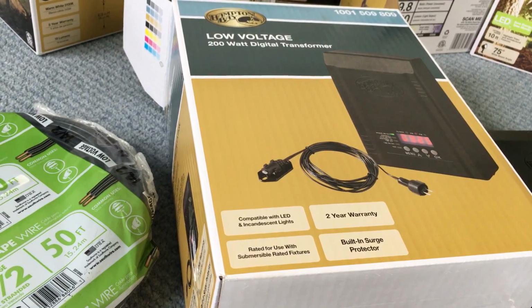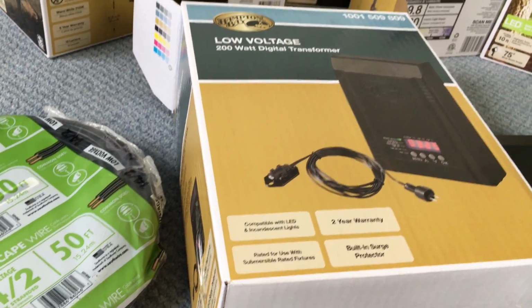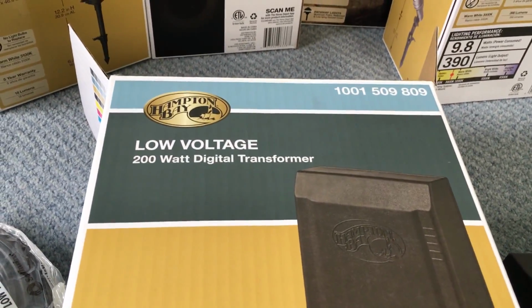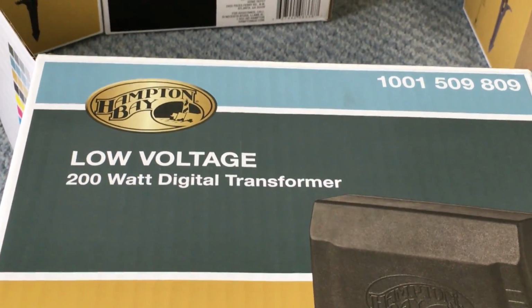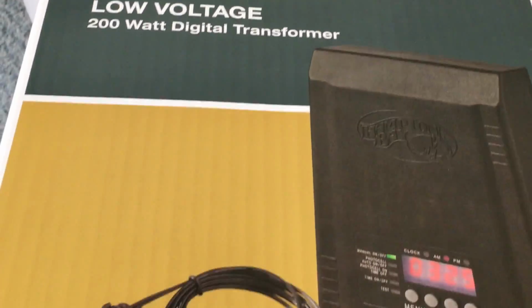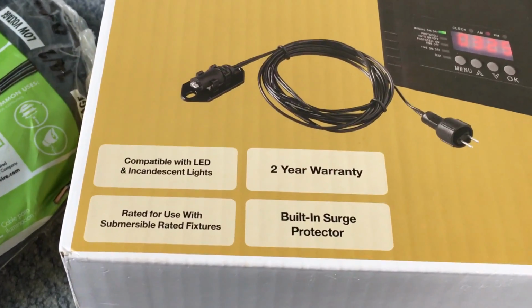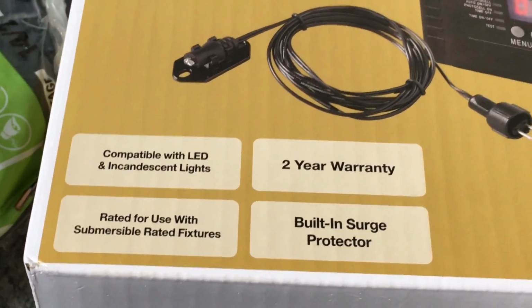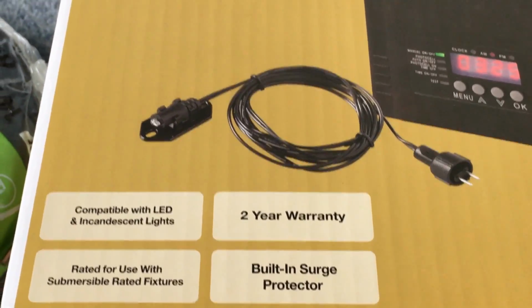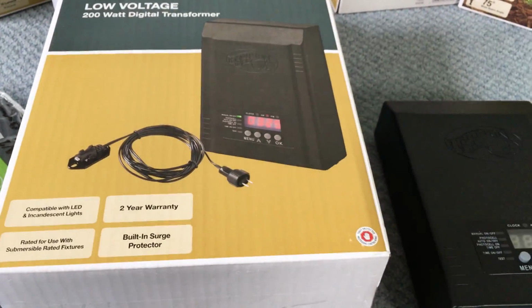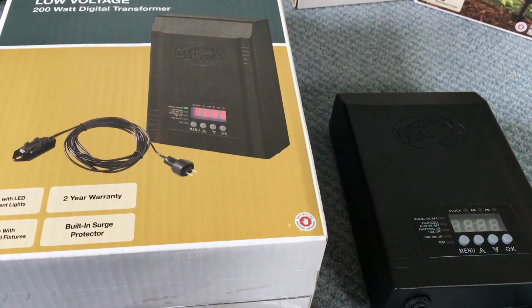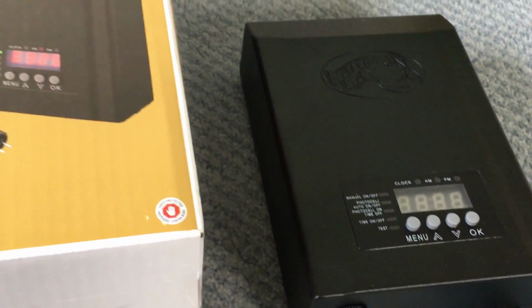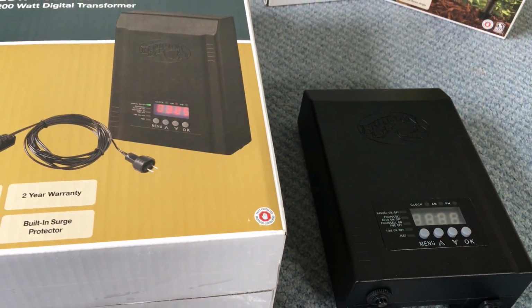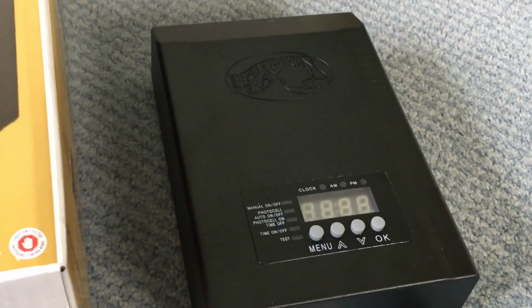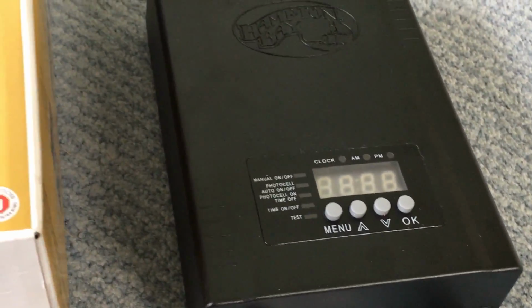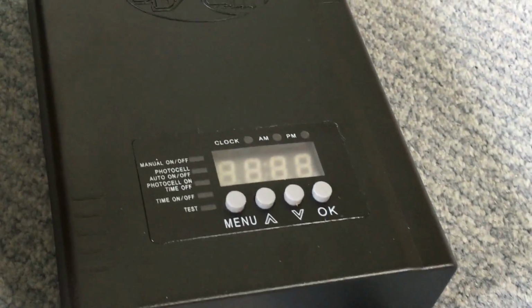This lets you safely supply power to the low voltage lights, in our case the outdoor light fixtures. The transformer I selected is the Home Depot brand Hampton Bay 200 watt digital transformer. One feature I liked is that it's rated for indoor or outdoor use, so if you don't have proper outdoor space you can install it in your basement, or outside if you have the space. In my case, I'm installing it outside.